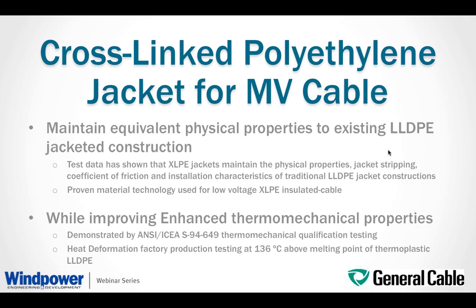So now we'll talk a little bit more about the jacket, and then the use of cross-linked polyethylene material as a jacket for the medium voltage collector cable. Linear low density polyethylene, LLDPE, has been the thermoplastic jacket material of choice for North American utility medium voltage primary distribution cables, primarily because of its good physical properties and relative low cost.